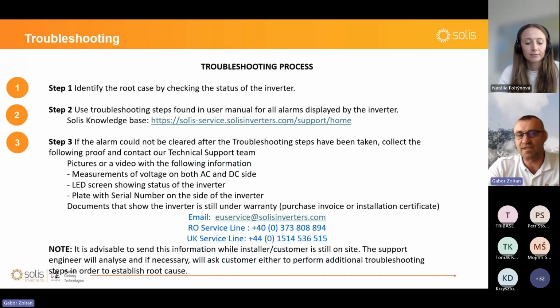During troubleshooting, as the first step, you can check the status of the inverter using the LCD or the Solis app. If you have any alarm, please first check the manual. You can reach all the manuals for all inverters on the solisinverters.com web page, and you can download all of them and check the alarm message and the necessary steps.